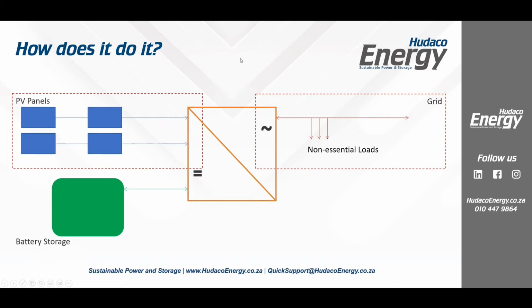On the battery side of things, we use a high voltage lithium ion system, and we say from 9.6 to 19.2 kilowatt hours of storage. Please note, this is usable energy. A lot of the other guys will say, well, we've got 12.8 kilowatt hours or 12 kilowatt hours, but you can only use 80% of it. Well, 12, if you can only use 80% of it, is actually 9.6. Every figure that we quote is always usable energy, not capacity. Okay, so please remember that, very, very important.